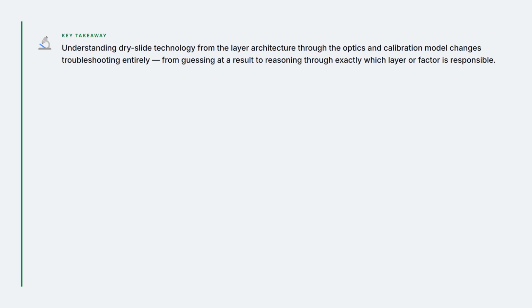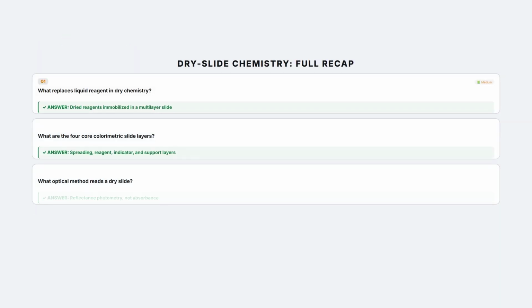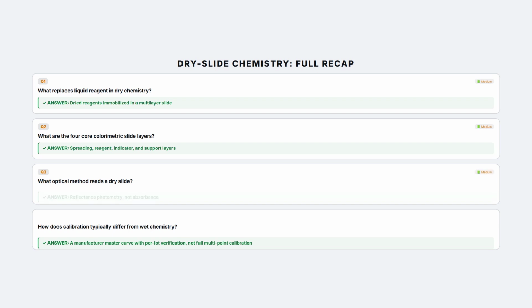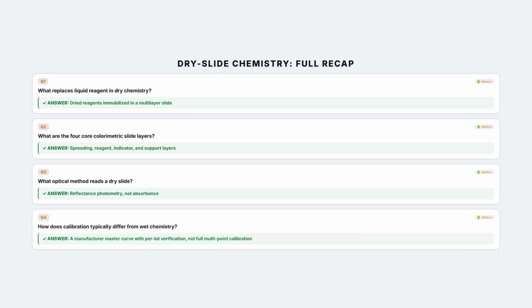Dry chemistry immobilizes reagents in a multilayer slide instead of using liquid reagent in a cuvette. The spreading, reagent, indicator, and support layers each perform one distinct function. Reflectance photometry, not absorbance, reads the result, following the non-linear Kubelka-Munk relationship. And most dry slide systems use a manufacturer master curve with per-lot verification rather than a full multi-point calibration.